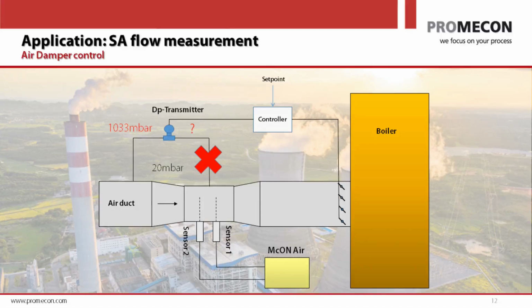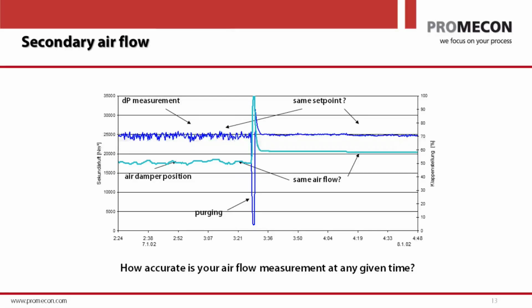He sees, let's say, 6 mills, and all 6 mills show an airflow that's pretty much the same, or that's pretty much what he expects. But what he is actually seeing are 6 set points. He doesn't see a true measurement. Let me show you this in another picture, what I mean by that. Right, and what this practically means, we can see on this slide. This is from a power station in Berlin. It's a coal-fired boiler, and it has 16 burners.